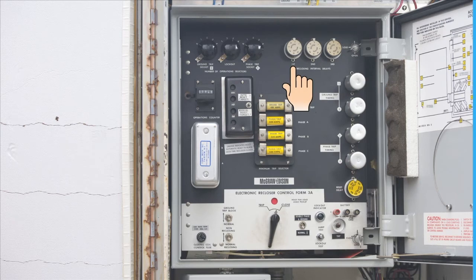If the overcurrent is cleared before the operating sequence reaches lockout, the reset delay circuit starts timing when the recloser closes into the unfaulted line. When the reset delay plug times out, the sequence relay is reset to the start or home position, and the control is ready for another 2 fast, 2 delayed trip operating sequence. However, should the fault restart before the reset plug times out, the control will continue its operating sequence where it left off last, and the reset delay timing will be erased.